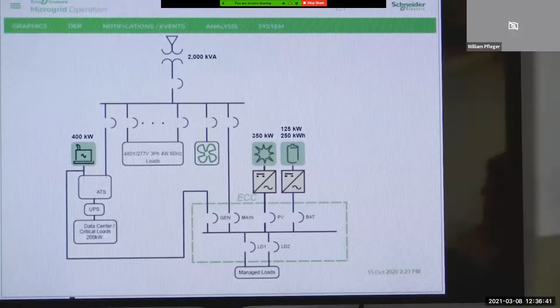So we put in an energy control center, the piece of equipment I'm standing next to, and we did some analysis of the loads that were going dark during an outage that were the most painful. And we found a couple of very important loads, one of which has a 200-person conference center. So we could have people travel here from all over the world to come to some event in our conference center. And if the power went down and we had them in the dark, we'd just have to send them back to their hotels. And that's not ideal, especially if you traveled from far away. And so that sector of the building is one of the things that we moved over into the ECC to become part of the microgrid.